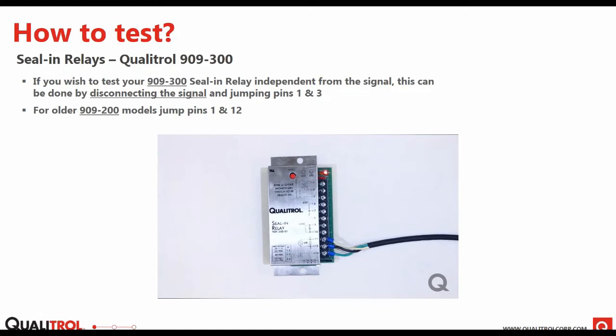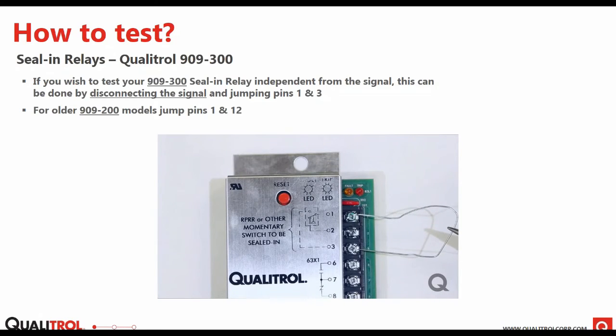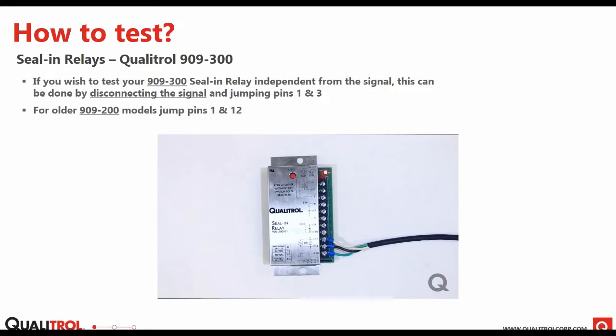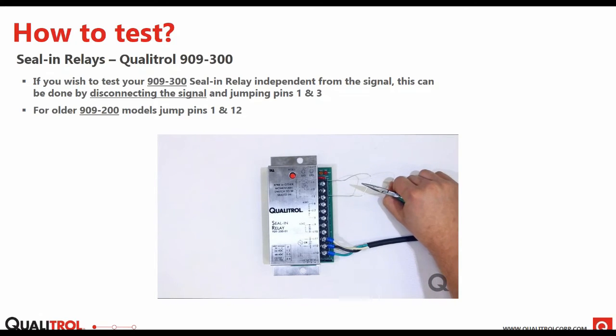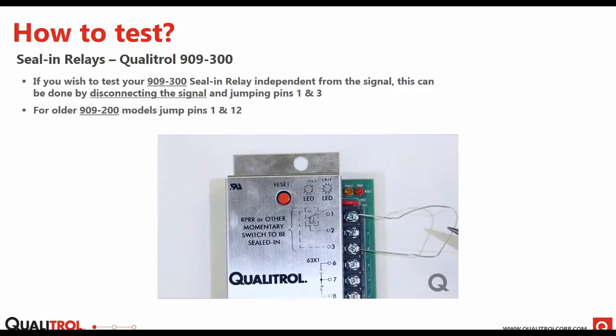This same simple test can be done on the 909-200, but instead of jumping terminals 1 and 3, you want to jump pins 1 and 12. You don't want to mix those up between the two models, so be sure to check which model you have before performing this test.